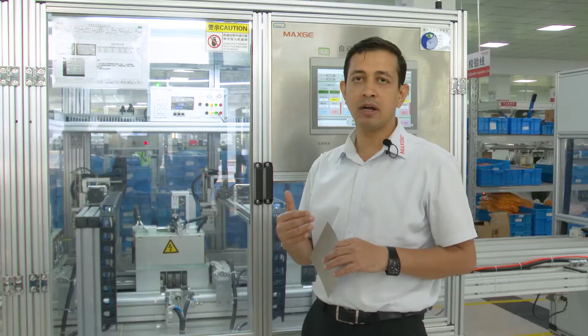After the demagnetization process is over, we do the first calibration of the RCCB. Again the residual tripping current is being applied. Here you can see there are 2 stations. In the first station there is a calibration, meaning we apply the residual tripping current and check whether the RCCB is tripping under that condition or not.